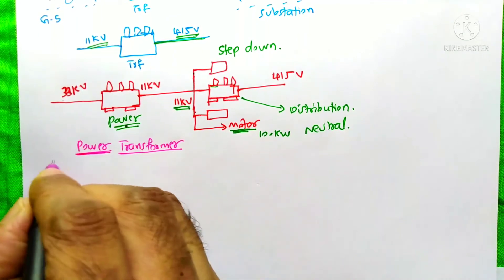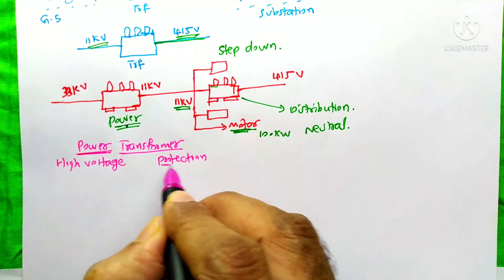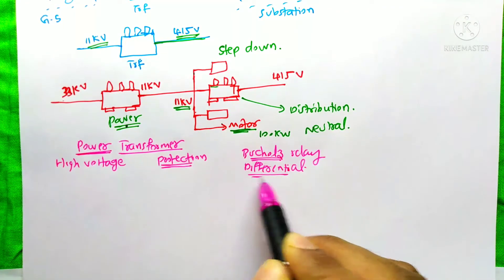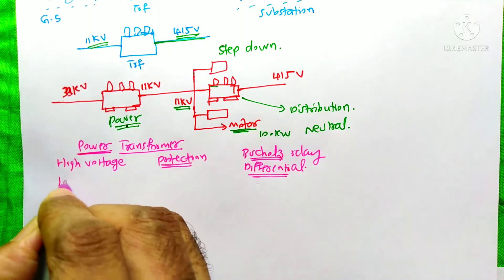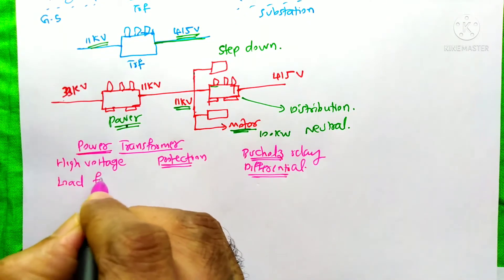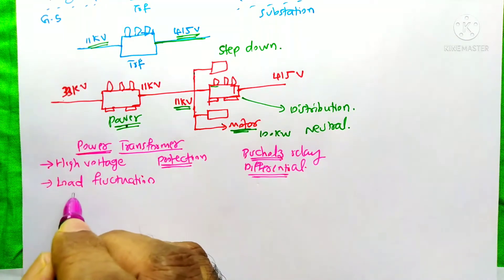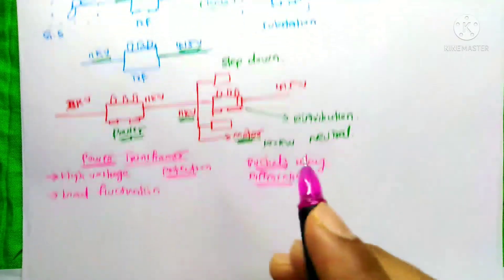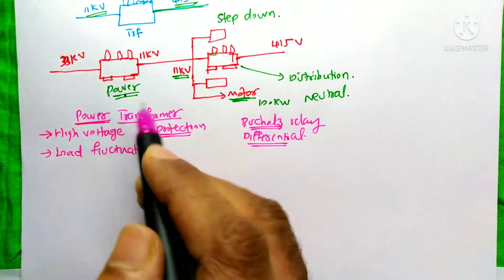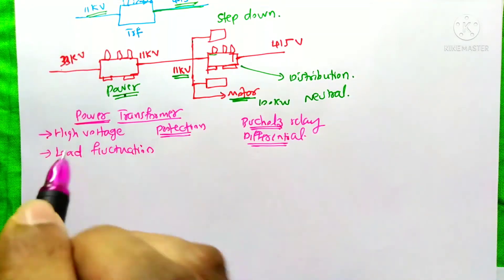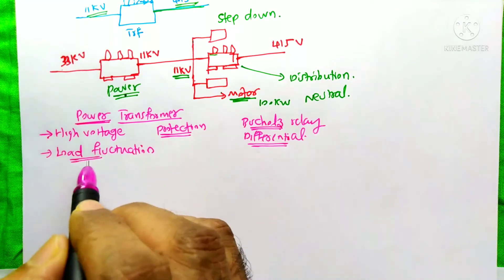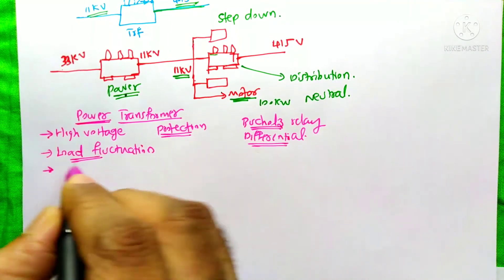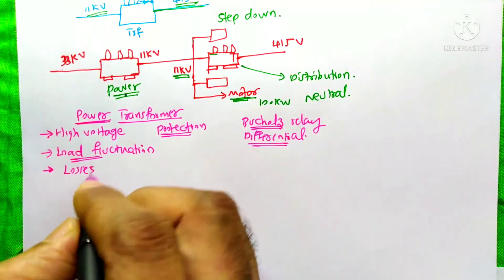The power transformer handles high voltage, so a high level of protection is needed — we are already familiar with the Buchholz relay and differential protection. The load fluctuation is very low in the case of the power transformer, because loads do not connect directly to it. Only in specific industrial cases, such as direct motor connection, would there be some load fluctuations; generally, load fluctuations are negligible. Due to these low load fluctuations, the losses in the power transformer are also very low.